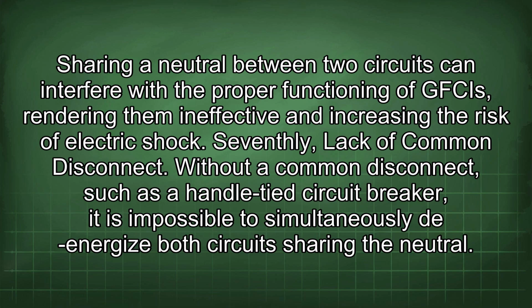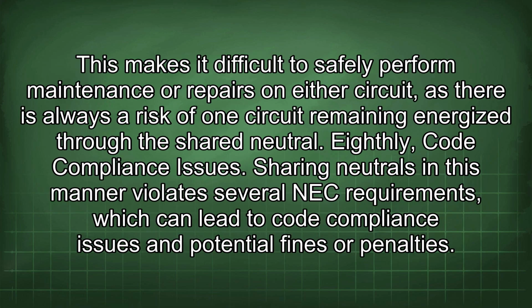Seventhly, lack of common disconnect. Without a common disconnect, such as a handle-tied circuit breaker, it is impossible to simultaneously de-energize both circuits sharing the neutral. This makes it difficult to safely perform maintenance or repairs on either circuit, as there's always a risk of one circuit remaining energized through the shared neutral.